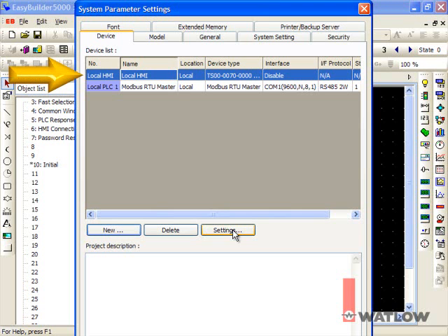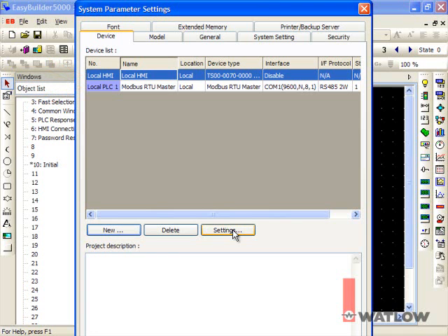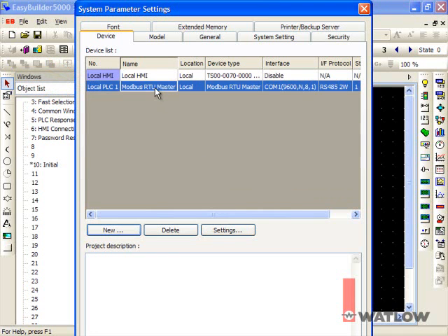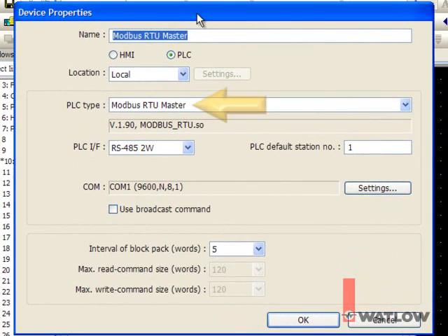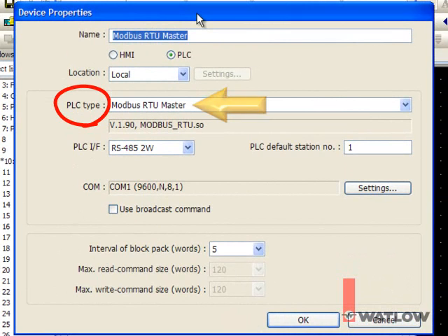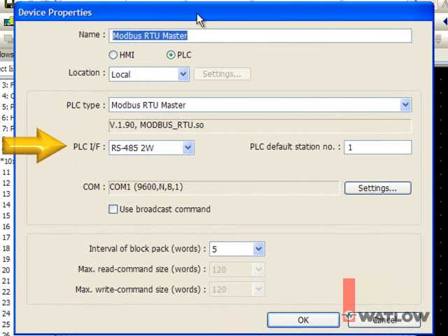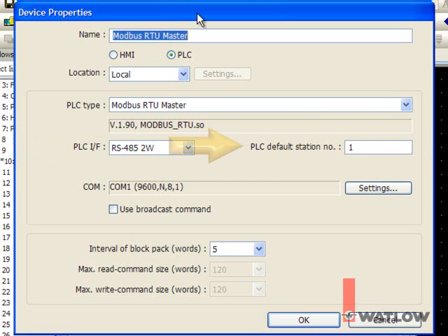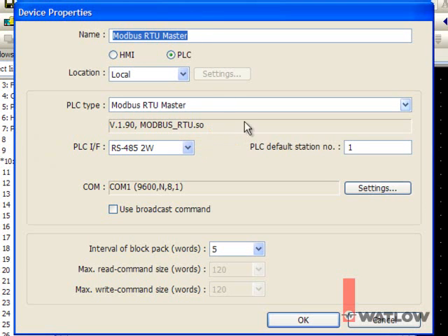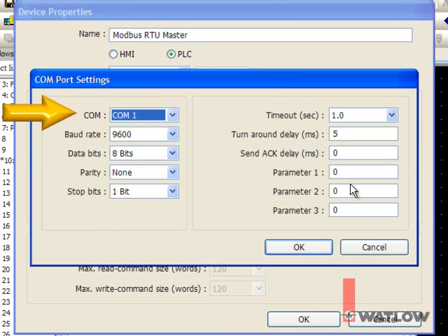Let's configure the Modbus RTU Master device by selecting it and clicking Settings. Modbus RTU Master is selected for PLC type. EasyBuilder 5000 refers to any device OITs communicate with as a PLC because that's a common type of device used with them. Use PLC interface to set which type of connection will be made between the OIT and the RUI. The RS-485 two-wire setting is what we'll use here. Set PLC default station number to the Modbus network address of the RUI gateway. The default setting 1 is good. Click Settings and select the COM port on the OIT to which you will connect the RUI.